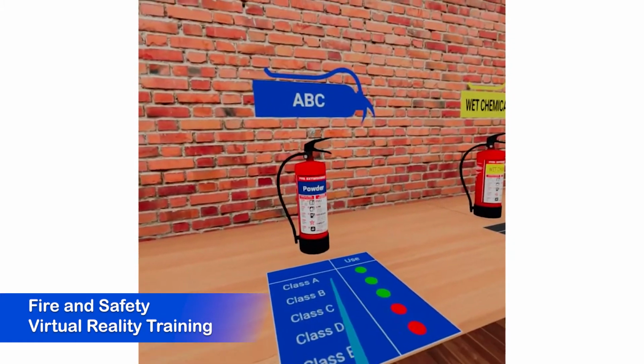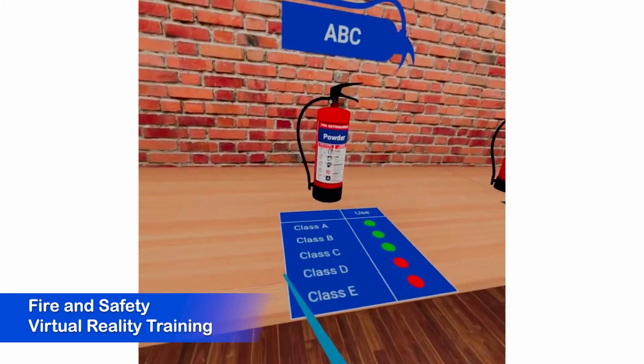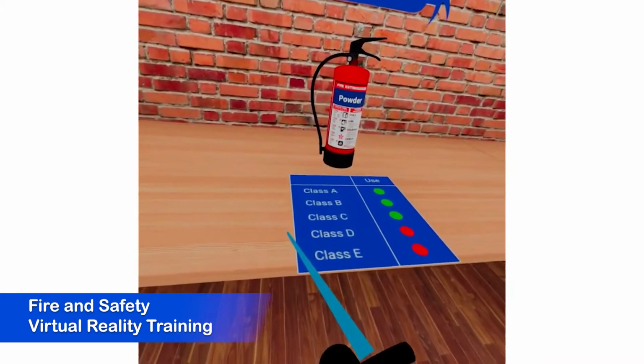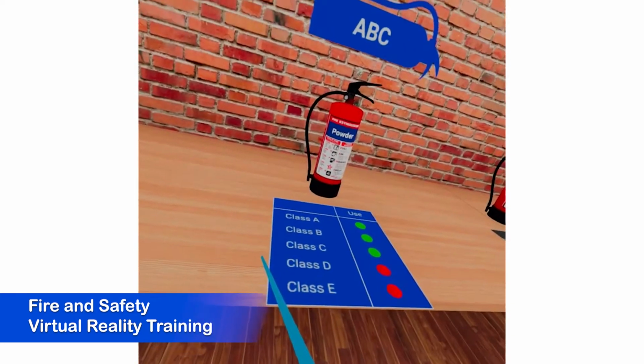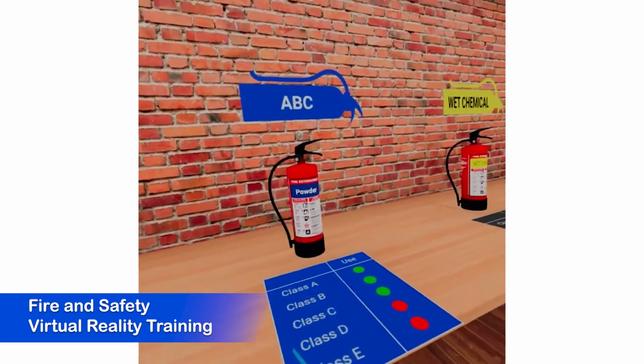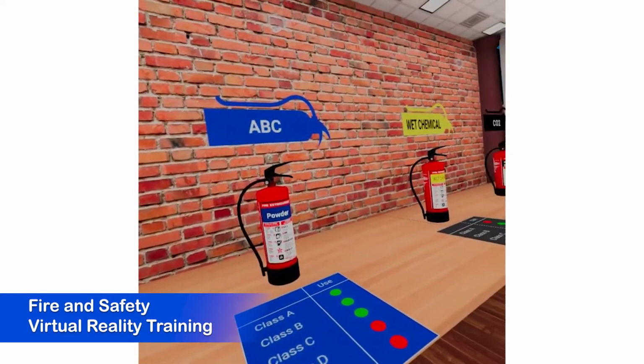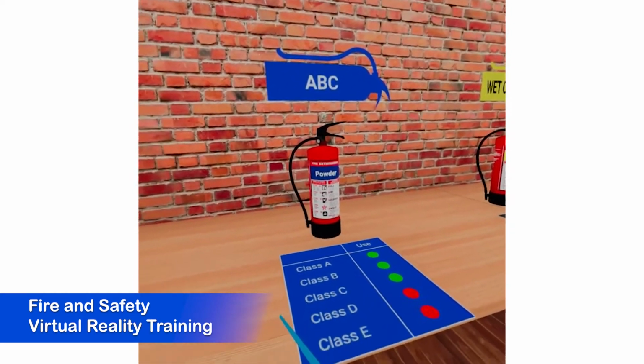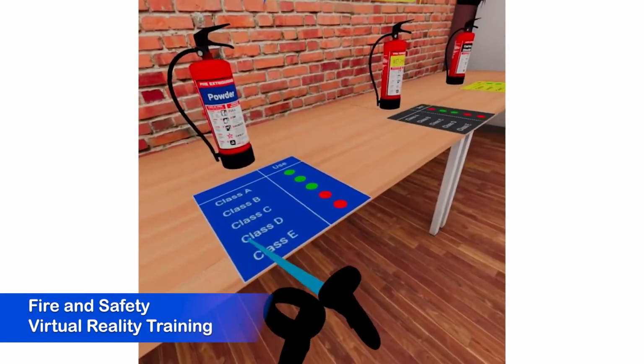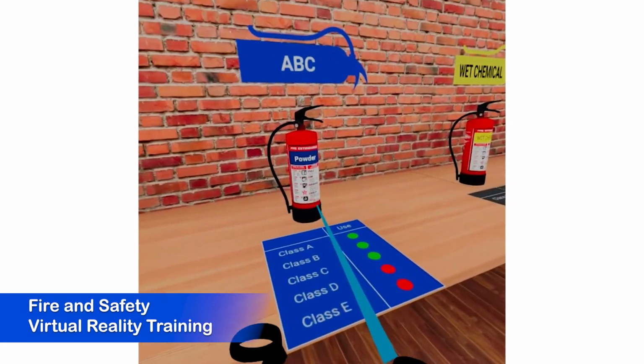Powder extinguishers are a good multi-purpose fire extinguisher, because they can be used on Class A, B and C fires. They can also be used on fires involving electrical equipment, however, they do not cool the fire, so it can reignite. Powder extinguishers have a blue label.